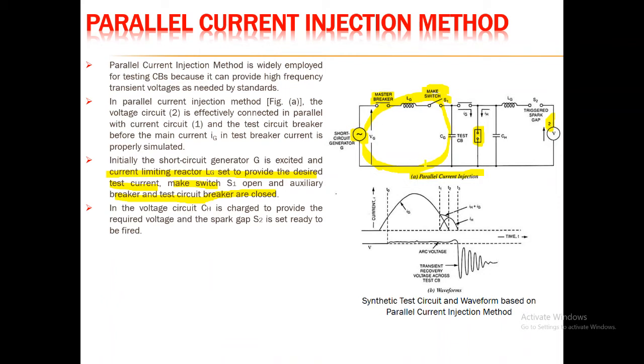In the voltage circuit, the capacitor CH is previously charged to provide the required voltage, and the spark gap S2 is set ready to be fired. When the current flowing in the short circuit loop approaches zero, this triggering gap must spark over. As a result, whatever energy has been stored by the high voltage capacitor CH will discharge its energy into the circuit breaker under test.